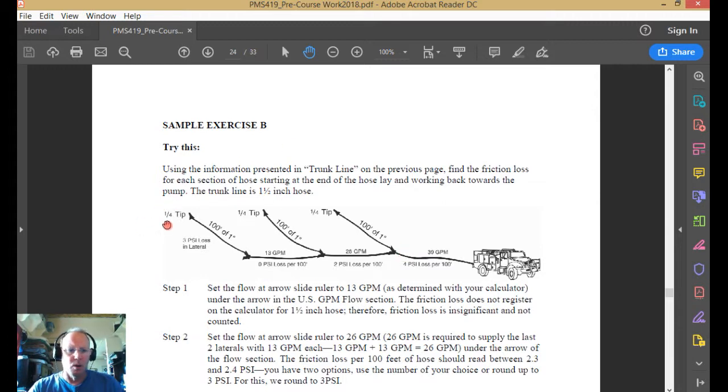You always start over here at the farthest lateral or what in the structure world talks about is you pump to the highest discharge pressure. And that's most notably always going to be the farthest nozzle away from the pump. I say most notably because that's the most common. You could have something that this nozzle is actually farther away, but let's say it's farther away in terms of horizontal distance, but it's down on the ground. Let's say that this nozzle here, the first nozzle, is closer to you, but now it goes up 150 feet.